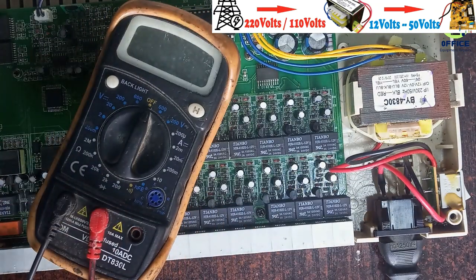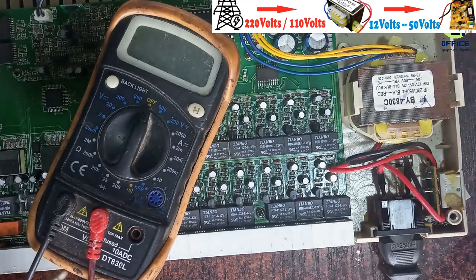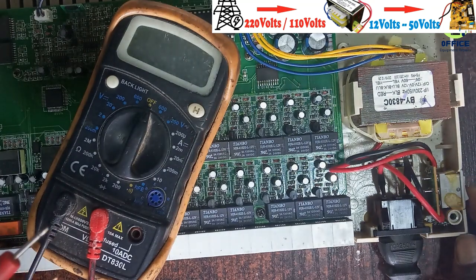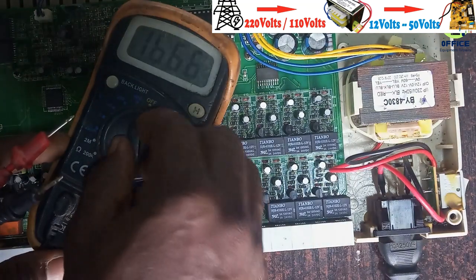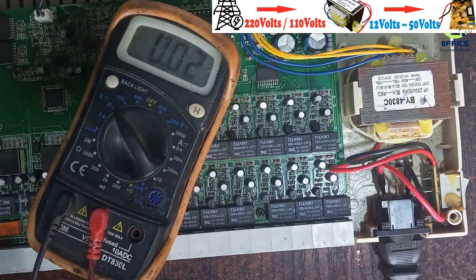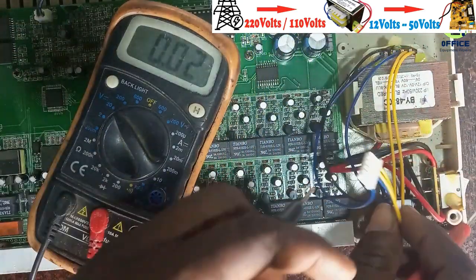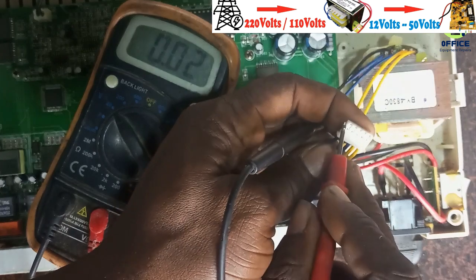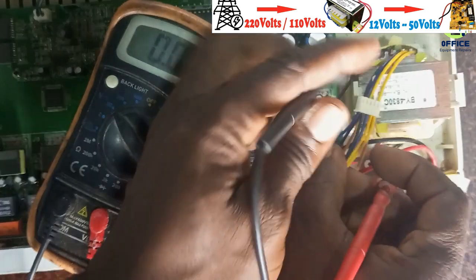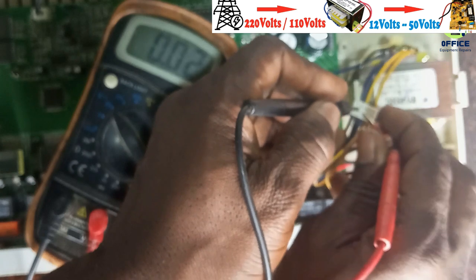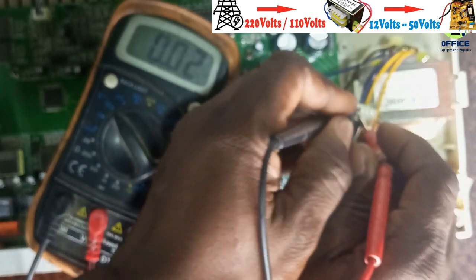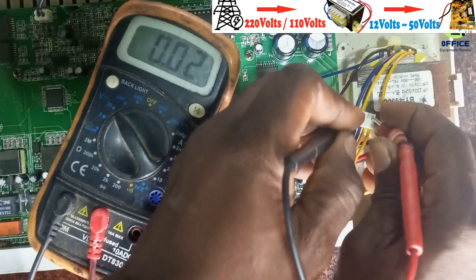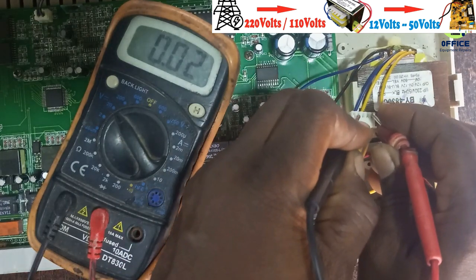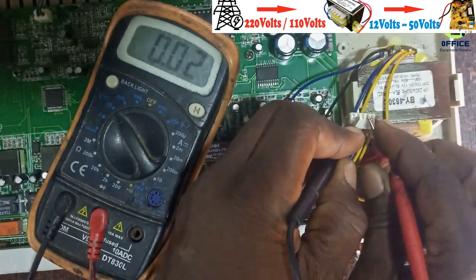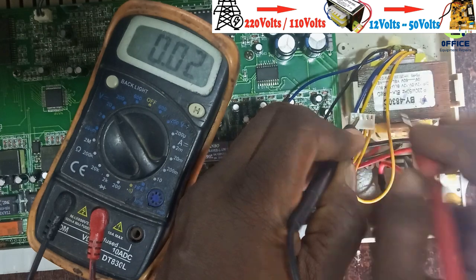So I'm going to do proper checking again just to be sure that power is coming into the transformer area. This is the contact point. I'm going to put the probe, one end in the negative side or the ground, then use the red end of the probe to test the other contact point and see if there is any voltage at all.